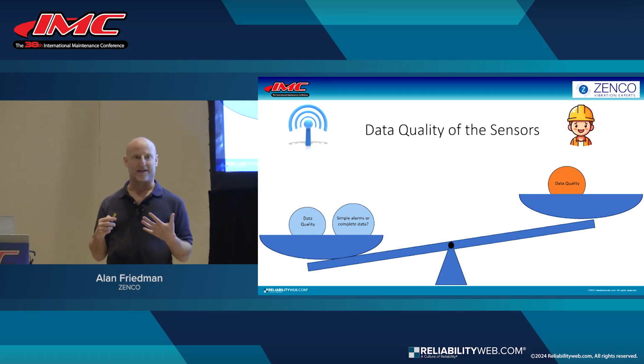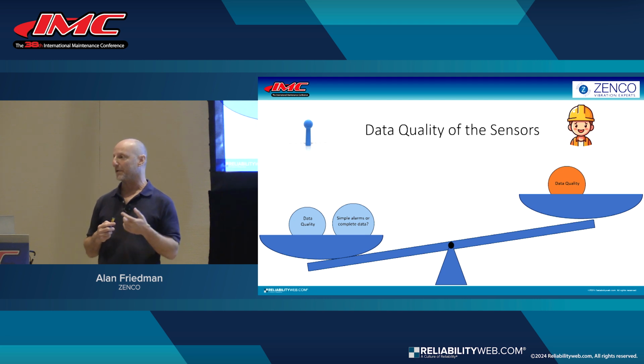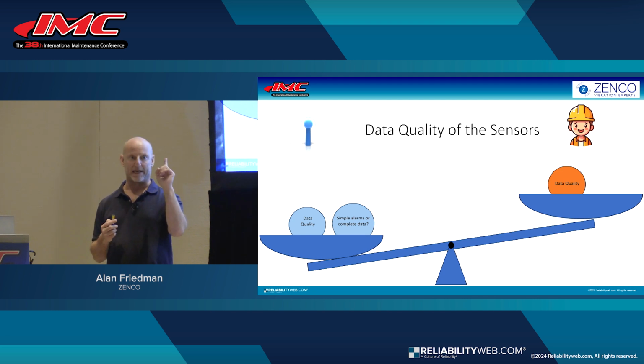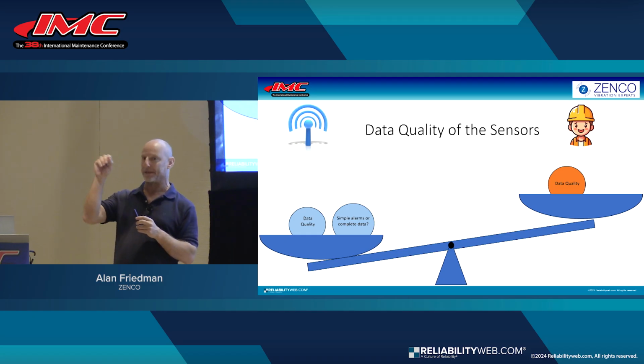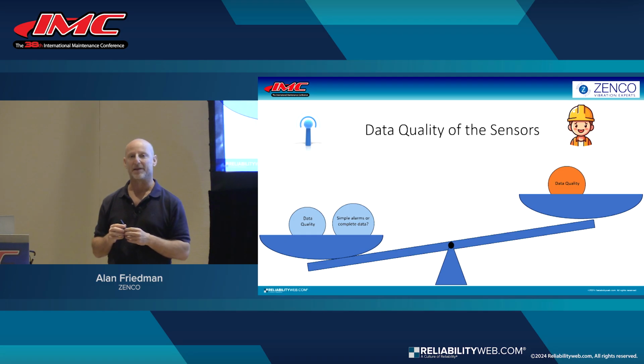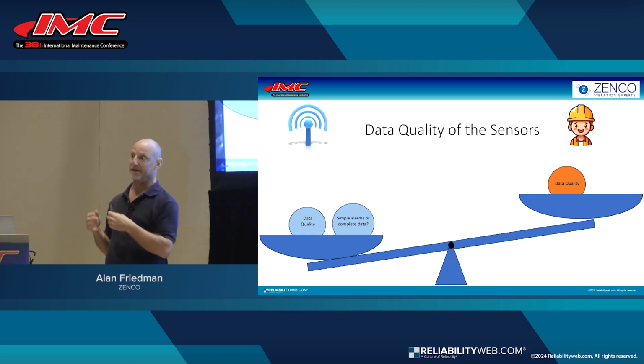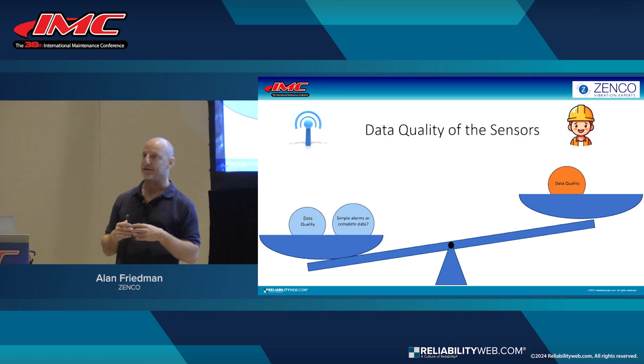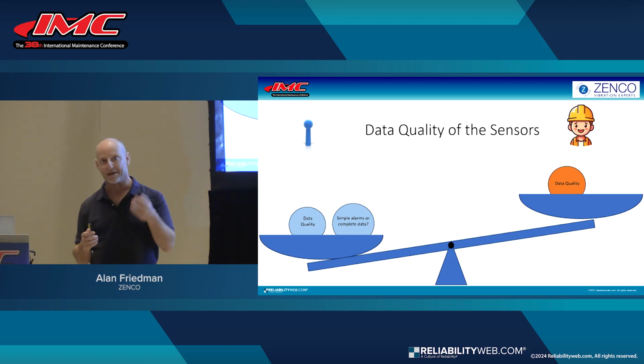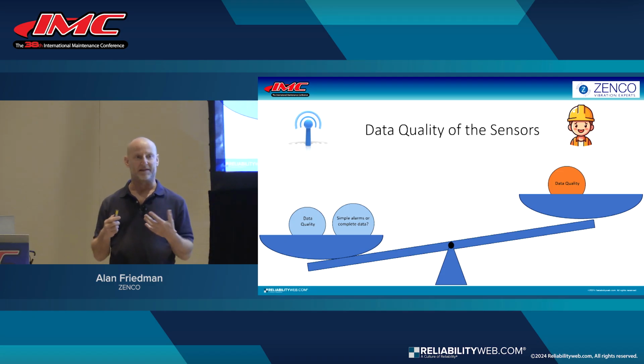There's another simple reading, an acceleration peak-to-peak reading, which is one number. It tells you if you have high-frequency pinging, like ping, ping, ping, ping, ping. That's something that happens when a rolling element bearing begins to fail at a very early stage. So that's something you could measure and send out as a value. It's also very easy and doesn't use a lot of battery.